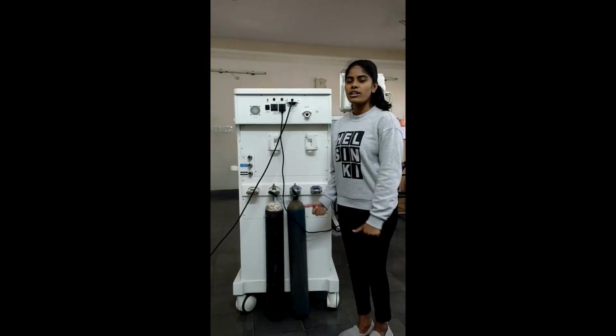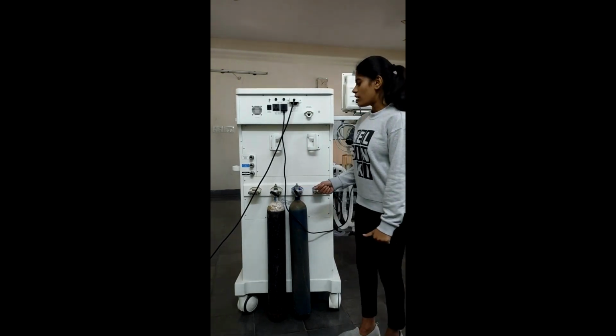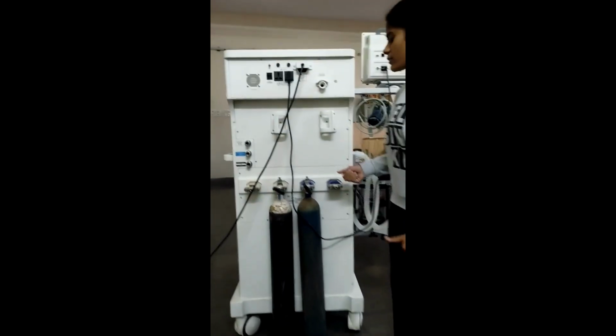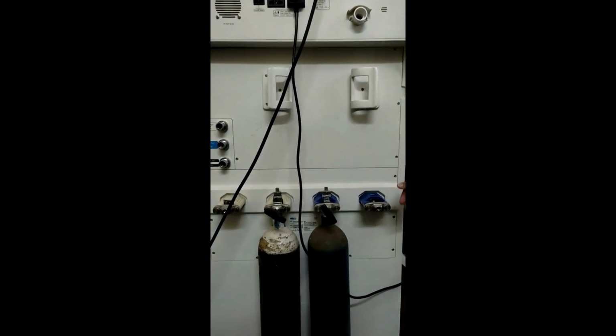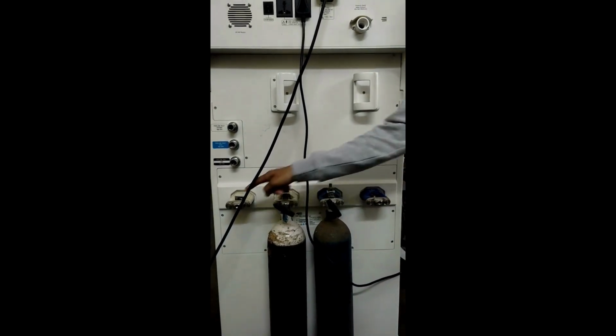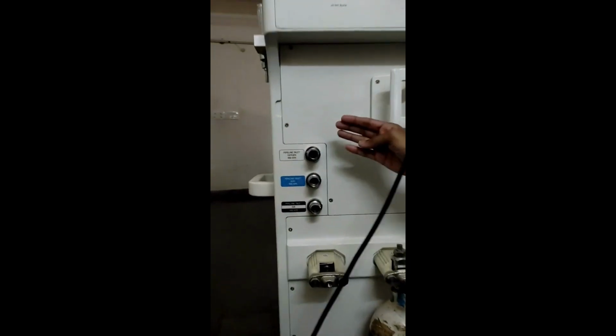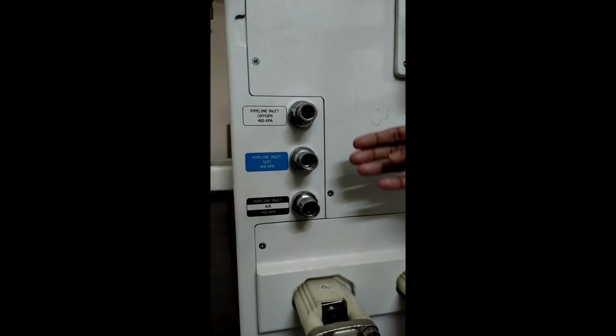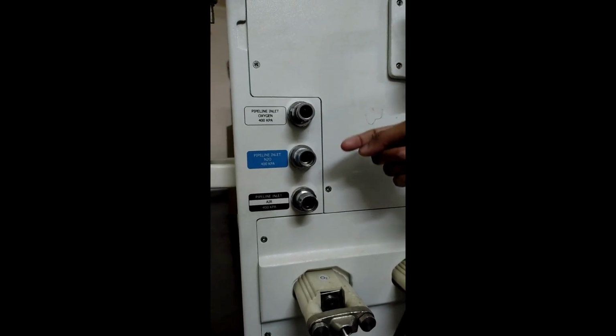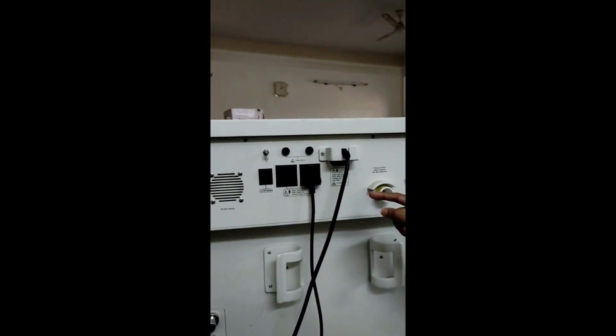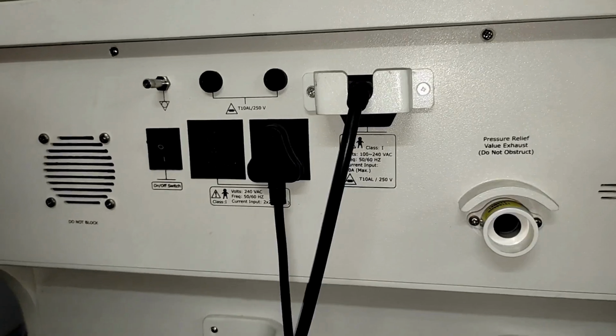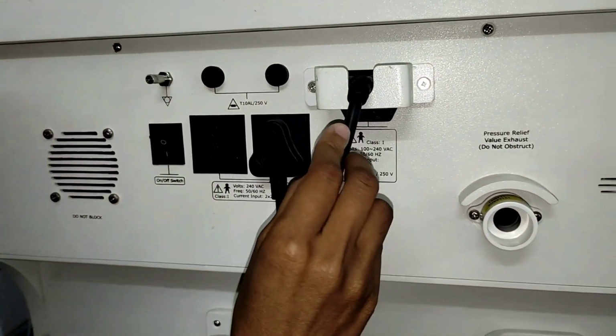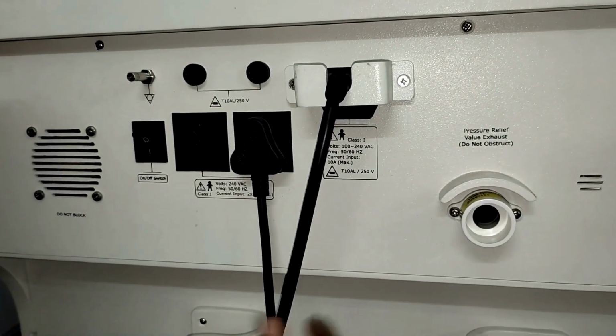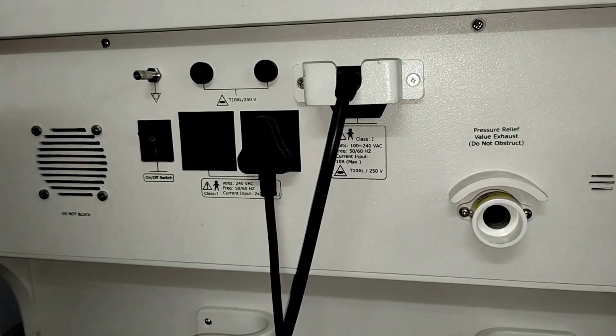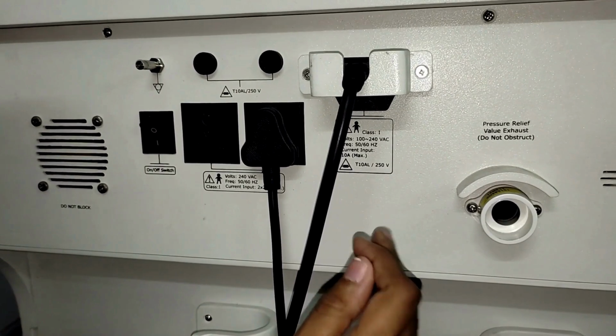This is the rear view of the anesthesia workstation. Here you can see the gas supply system. Here we have 4 cylinder yokes. 2 are for nitrous oxide, these 2 are for oxygen. Here we have 3 pipeline inlets. One is for oxygen, one is for nitrous oxide, and one is for air. Here we have 2 electrical outlets. This is the main supply to the anesthesia workstation, which operates in the range of 100 to 240 volts AC, and the operating frequency is 50 to 60 Hz.